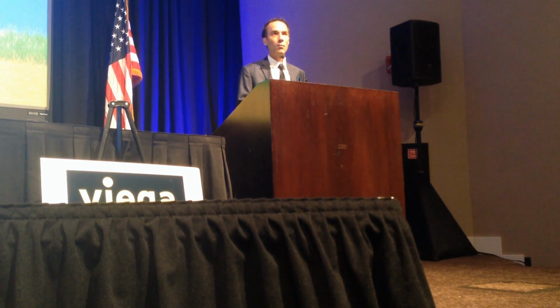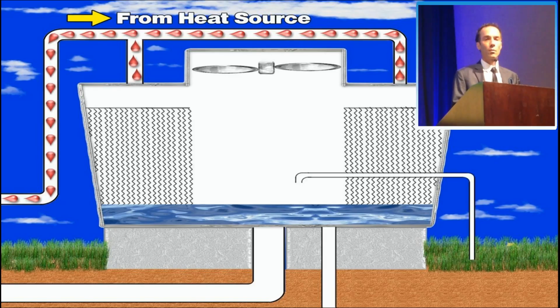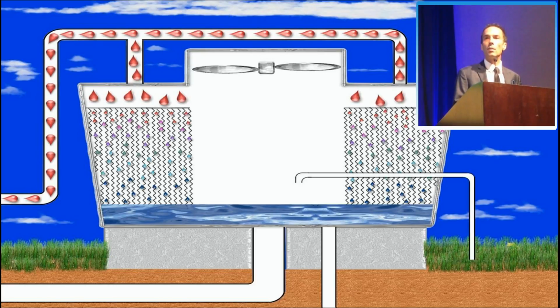For those of you that don't necessarily know how a cooling tower works, I'm going to give you a brief overview. Cooling towers are used in process, or in cooling large buildings, as has been referenced here quite a lot. The water from the heat source comes into the cooling tower through the top generally and disperses over the fill, and it starts to cool.